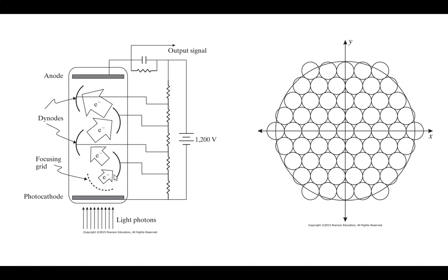Okay, quick things on how the rest of these work. So, photomultiplier tube, right? A light photon comes in, there's a photocathode, the photon hits it and releases an electron, right? Maybe one, maybe two, whatever. There's a little bit of a focusing grid, so we put a charge across this and it basically pulls the electron through, and we'll aim it right at the curved one here. And if you notice, there's this cascade, which means there's a voltage difference all the way down.